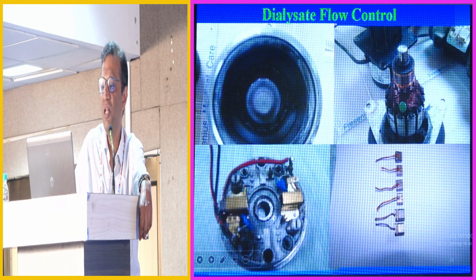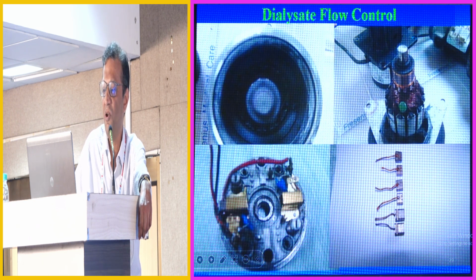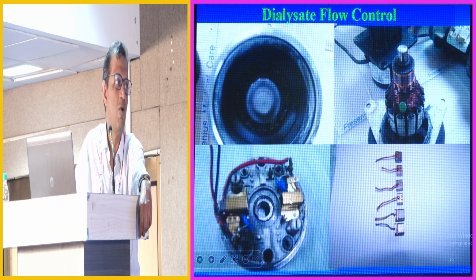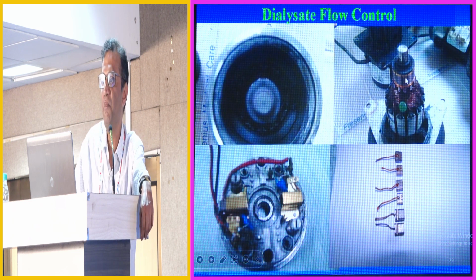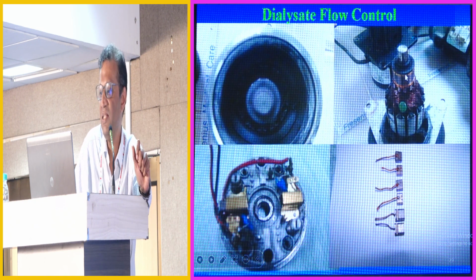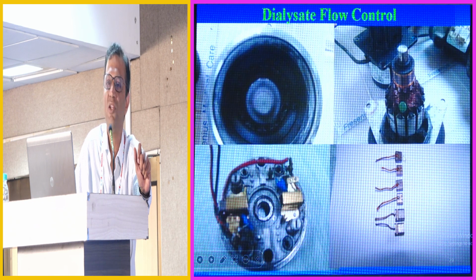The 24-volt DC supply is delivered to the motor by these 2 wires, the red and the black, and on each of these posts, within these two brass housings, we place these carbon brushes, and they make contact. The wire is connected here, and there's a spring that holds the carbon brush in place, and it makes contact with the armature of the motor here. As the motor rotates, as I said, it will wear down the brush in this fashion.